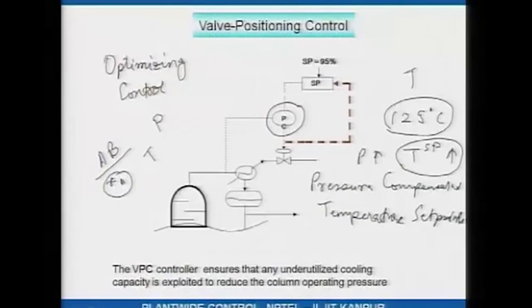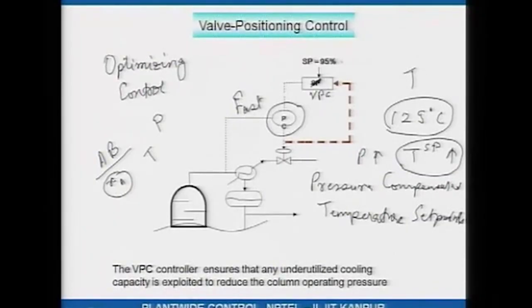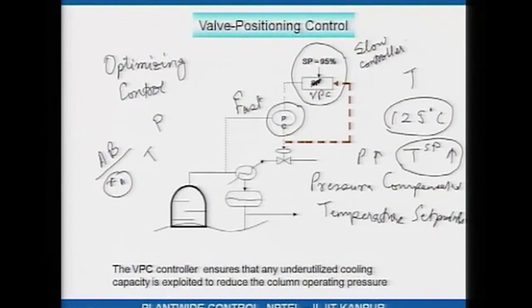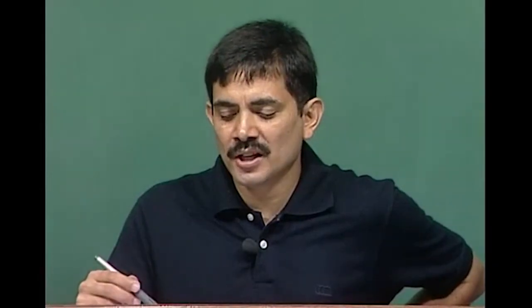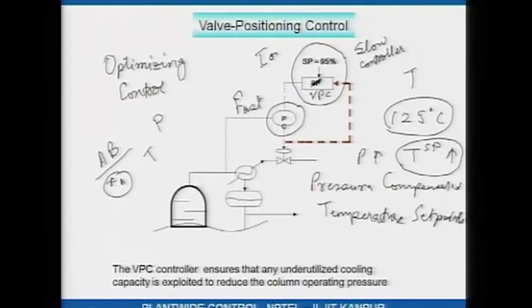Another thing to highlight: this pressure controller is fast — tuned for a fast and snappy response — while this valve positioning controller would be tuned for a very slow response. What that means is you do not want to change the pressure set point too quickly. You change the pressure set point slowly but surely, and the pressure controller action causes the cooling water valve to open. Since it is supposed to be a slow controller, many valve positioning controllers are integral-only — just a slow integrator.